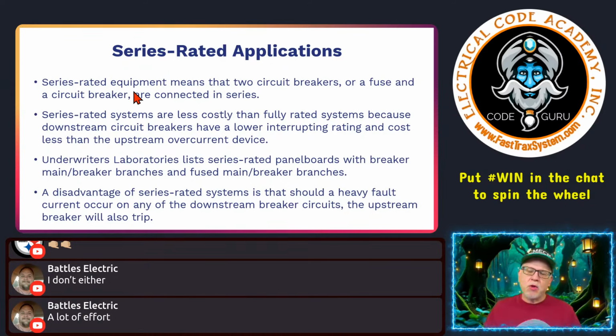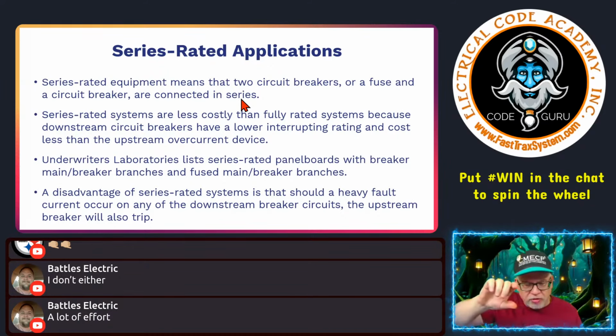Okay, so if you have a piece of equipment, and most of the panels that you're going to run into with a main breaker and then a bus, and they got the breakers that snap onto the bus, okay, are going to be what's called series rated equipment. Means that the two circuit breakers or a fuse and a circuit breaker are connected in series. Okay, so power comes in, hits a main breaker, continues through that main breaker, comes down and hits the bus, and then it goes through the circuit breaker that's mounted on the bus out to the branch circuit that's out to the load, right?